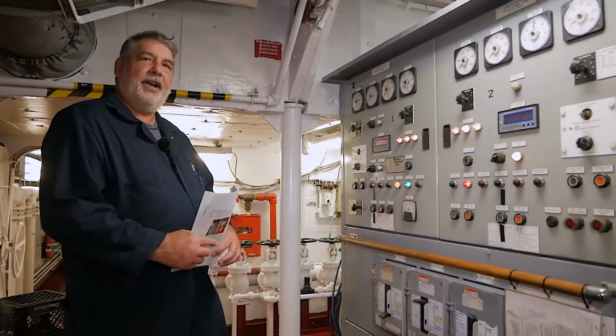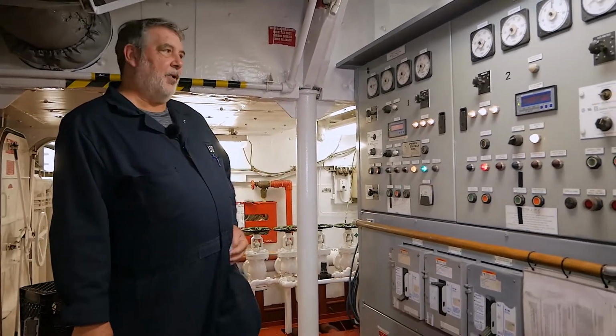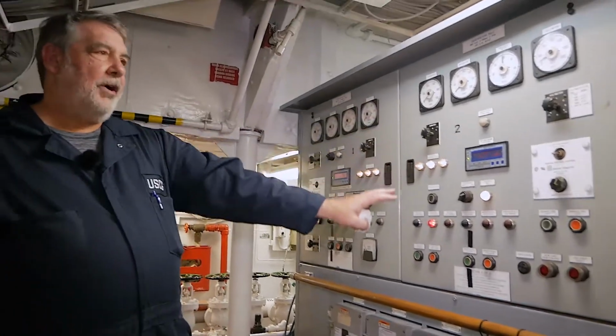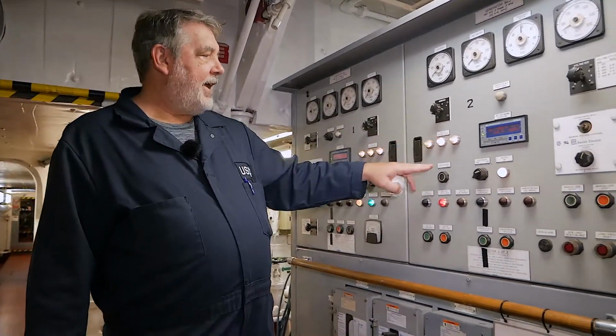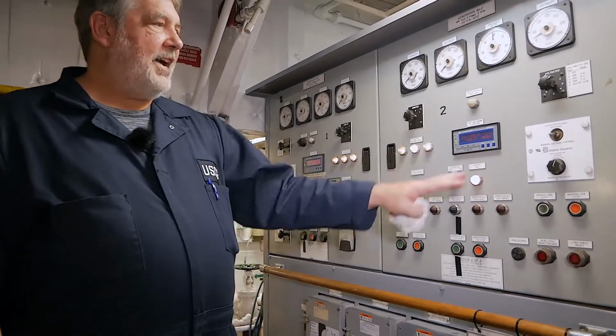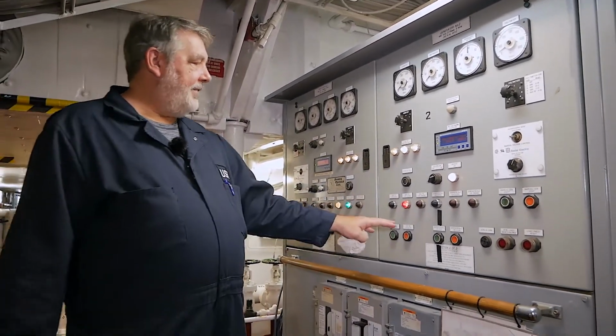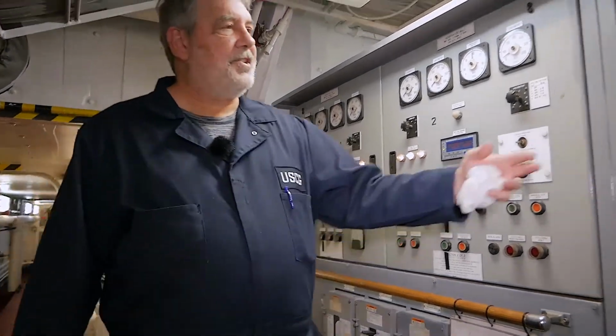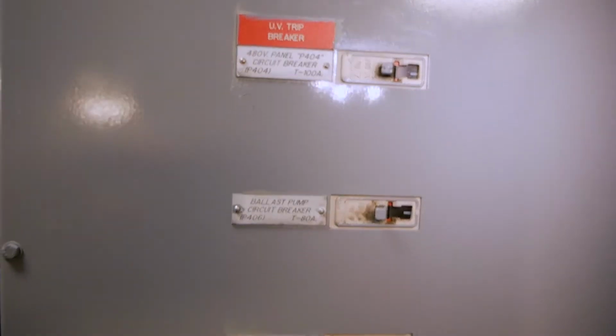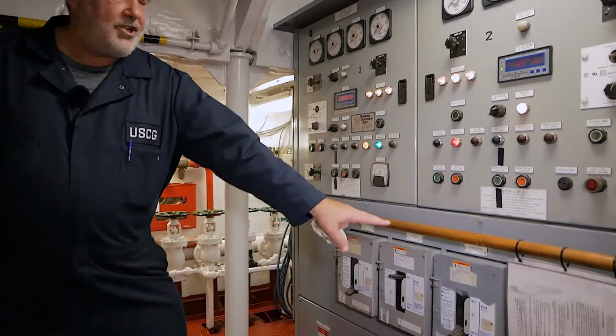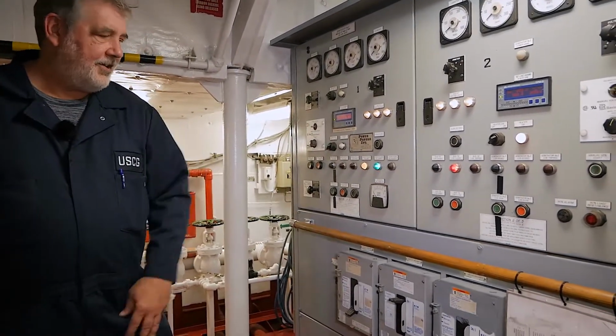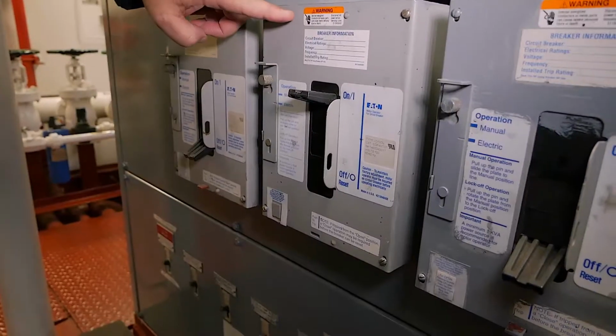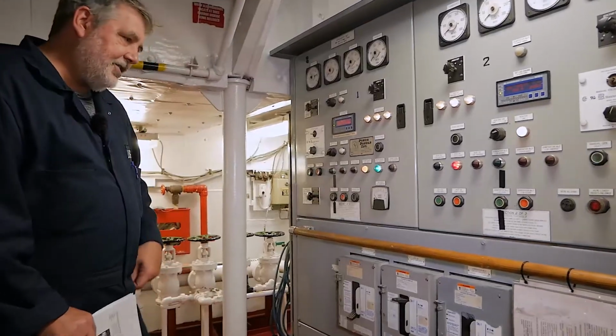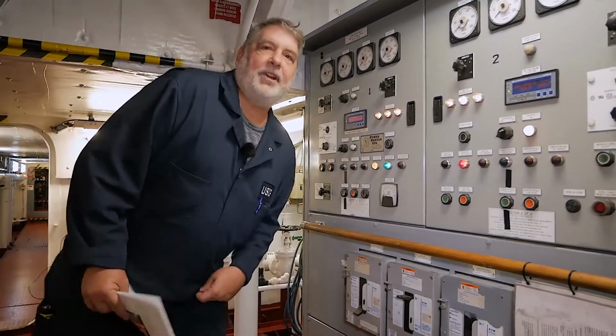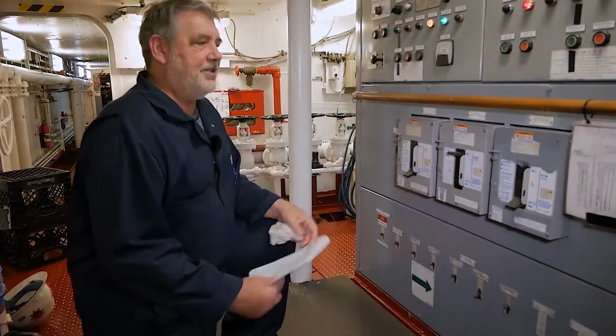Let's talk about breaker and component labeling on the switchboard. As you can see, all the components we spoke of earlier are labeled properly. This is a nice new switchboard and everything is properly labeled. Additionally, all the breakers are properly labeled and the ampacity is labeled on there. We have the main generator breakers and the shore power breakers here. As you can see, they all have the warning stickers or indicators on them. And these particular breakers also have locking devices.